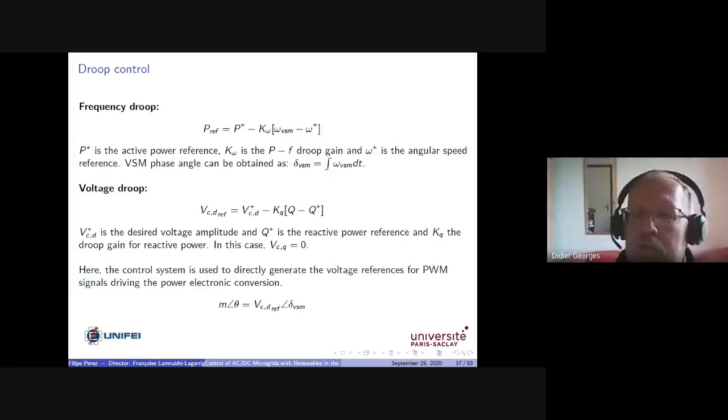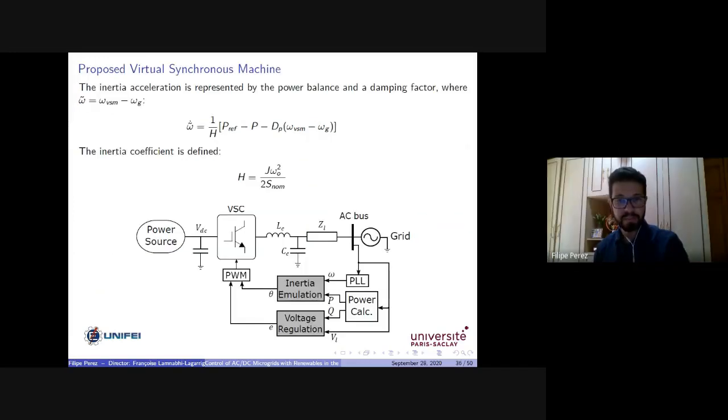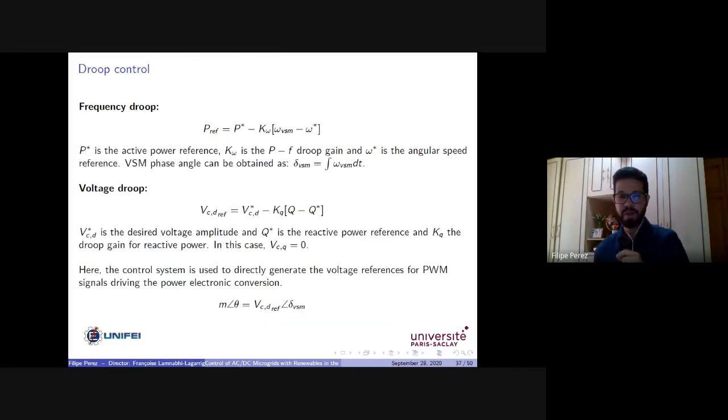I'm not sure. Yeah. So I have two variables here actually. One is the delta, and delta is the difference angle between the delta from the grid and the delta produced by the virtual synchronous machine. As in the swing equation, here I have omega VSM minus omega grid.